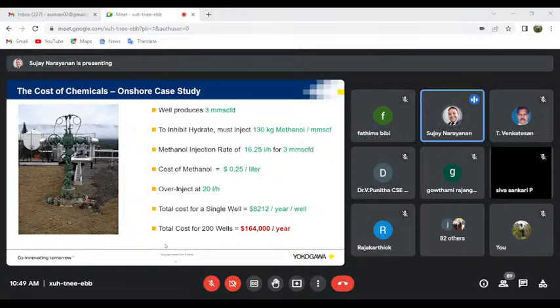Now, it's impossible for an operator to set an injection rate of 16.25 liters an hour. So the operator blindly rounds up to 20 liters per hour because he wants to overdose, because underdosing will cause production stoppage, for the obvious reasons I said.